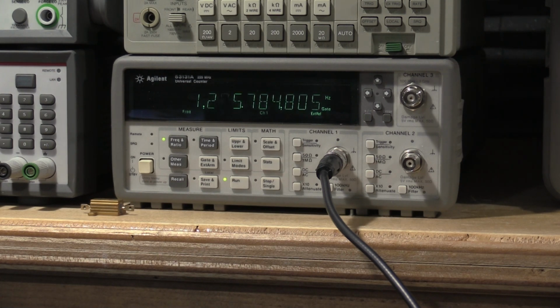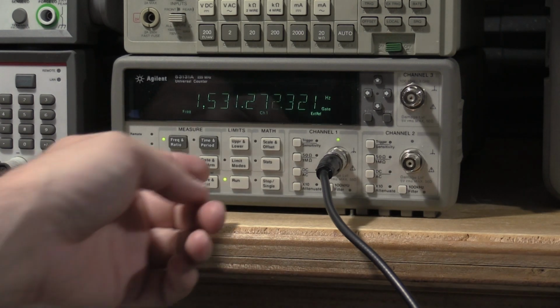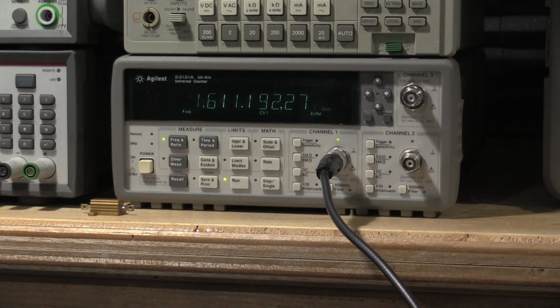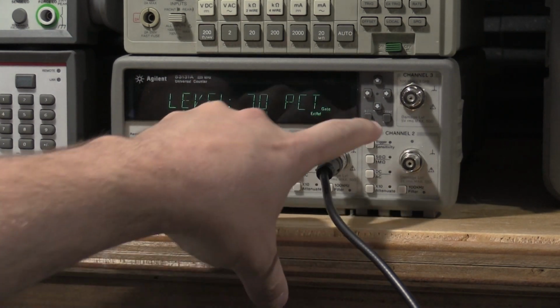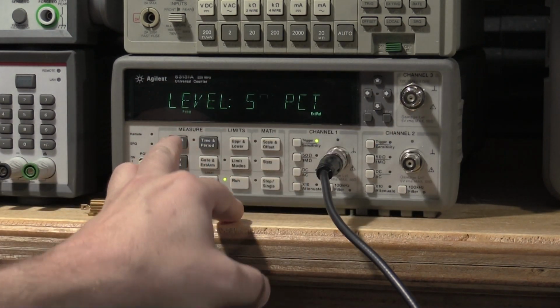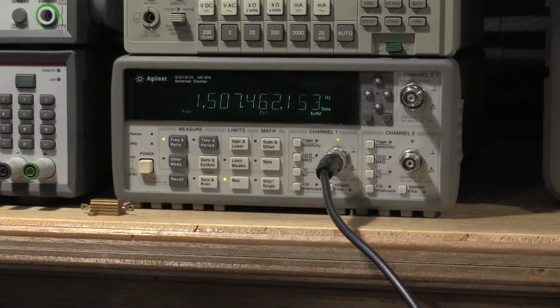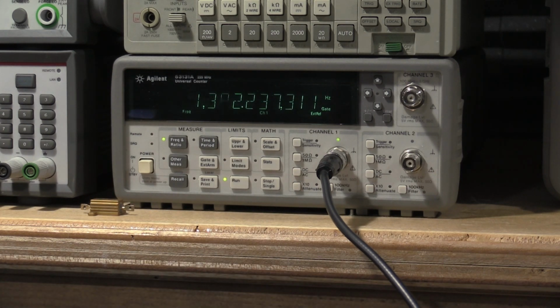No, negative 8 dBm into 600 ohms. So we have plenty of signal for driving the frequency counter. I have the trigger set to 70%. We can even lower this to 50%. But problem number one is the frequency is not stable at all. It's bouncing around pretty good. So that's going to cause some problems when aligning AA501s and a few other things.